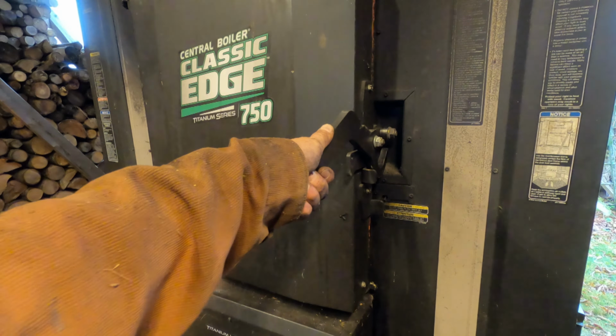I did research that. It's better to have it on the inlet side rather than the outlet side. It might be more important if you didn't have that aquastat that I just mentioned, because it could be that the boiler doesn't see that it's up to temperature if you have the heat exchanger on the outfeed side, because the water coming back will be cooler and the oil boiler might still fire. But here, feeding that heat into the system on the inlet side, if you didn't have that aquastat that I put in, then that would basically tell the boiler, okay, I'm up to temperature, I don't need to fire, as long as it's maintained the heat from the outdoor wood boiler. If that makes sense, hopefully it does. A lot of gibberish. I'll do one more look out at the boiler and we'll wrap it up.